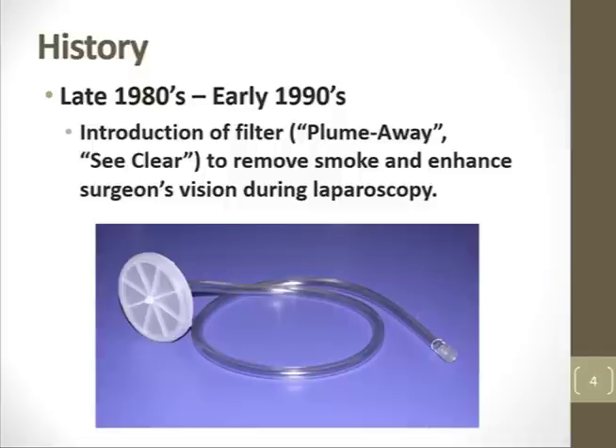In the late 80s into the early 90s, the first smoke capture device was actually a smoke filtering device, which involved, as this picture indicates, simply a housing containing a HEPA filter and an activated charcoal disc, and it was used to remove smoke during laparoscopy. Now, normally, one would think that this device was invented to prevent you from breathing in smoke that would be vented through one of the side vents of a trocar. But actually, what it evolved into was a visualization enhancing device, because without the smoke in the abdomen, you could see better and not have to clean the lens. We all know that you take the warm lens out of the abdomen, expose it to the cold air, and then put it back into the abdomen after cleaning it, and now you have condensation on the lens to deal with as well.